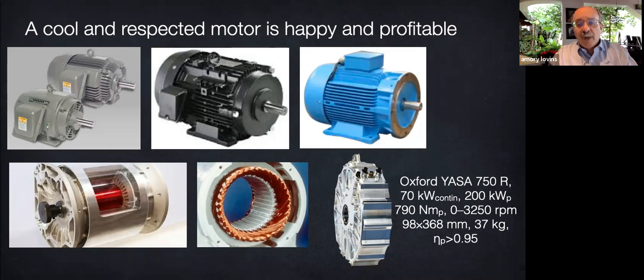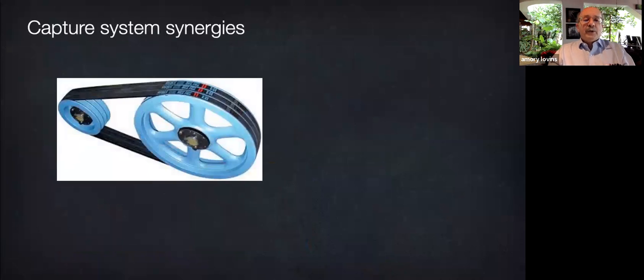Performance is regularly measured and tracked with barcodes. Rewinds are very rare. They're non-destructive and they're monitored. You don't put the motor back in service until you're sure it didn't get damaged. And everyone has to keep up with progress, reviewing purchasing and lubricants at least annually. A company that still buys motors the way it did 20 years ago is leaving a whole lot of money on the table. Whole system thinking can also capture vital system synergies.